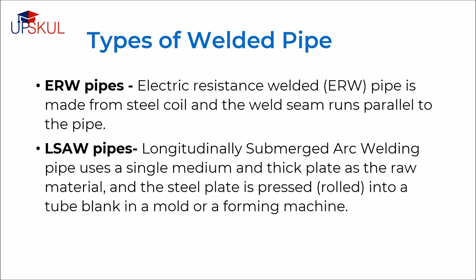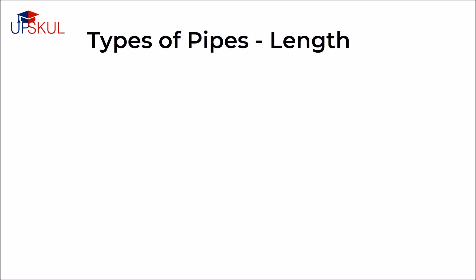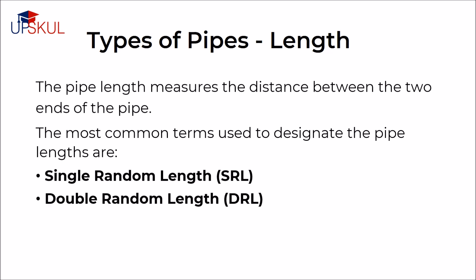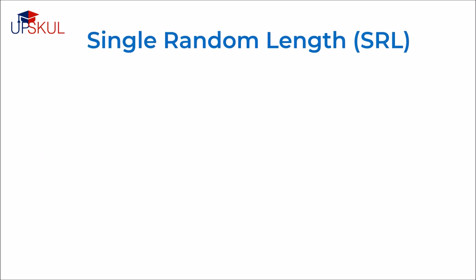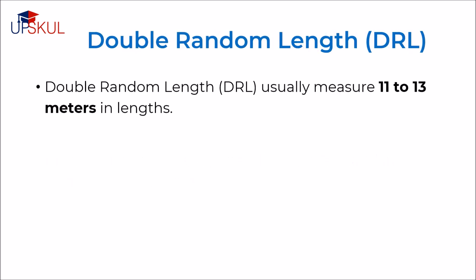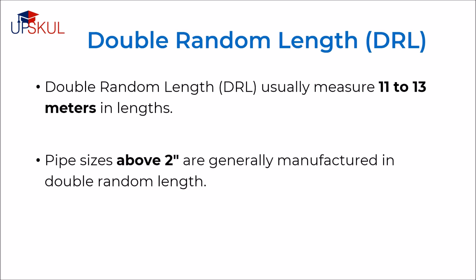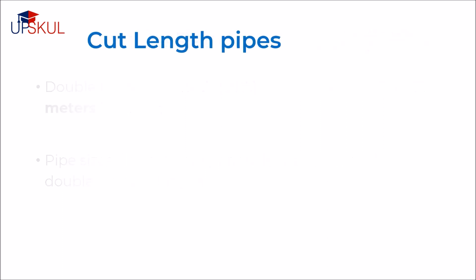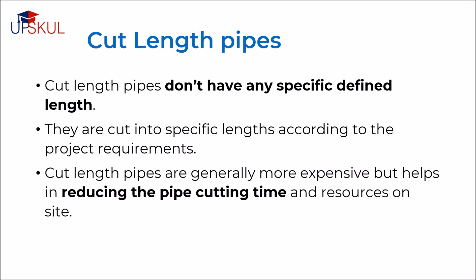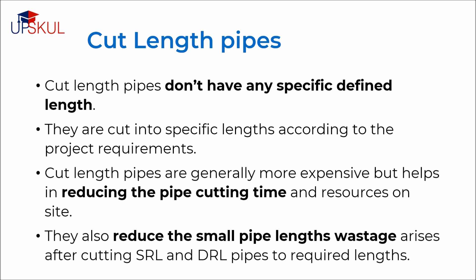The pipe length measures the distance between the two ends of the pipe. The most common terms used to designate the pipe length are single random length, double random length, and cut length. Single random length usually measures 5 to 7 meters in length, and pipe sizes below 2 inches are generally manufactured in single random length. Double random length usually measures 11 to 13 meters in length and pipe sizes above 2 inches are manufactured this way. Cut length pipes do not have any specified defined length — they are cut into specific lengths according to the project requirements. Cut length pipes are generally more expensive but help in reducing pipe cutting time and resources on site, and also reduce the small pipe length waste that arises after cutting single and double random length pipes.